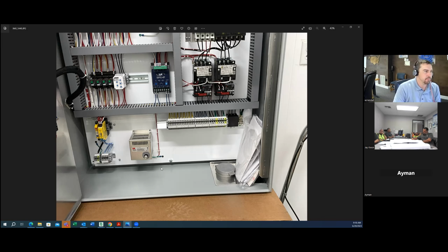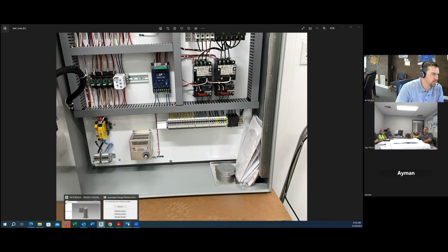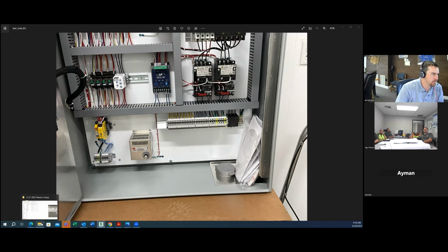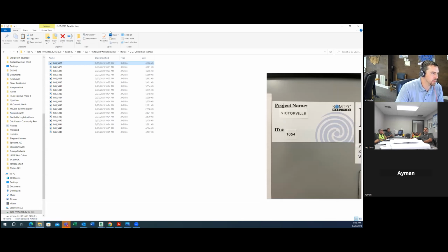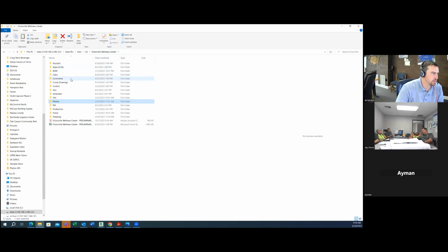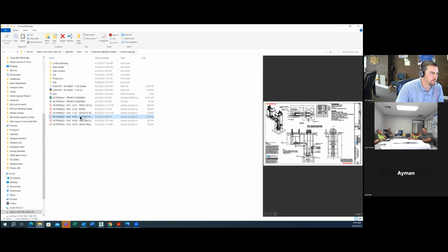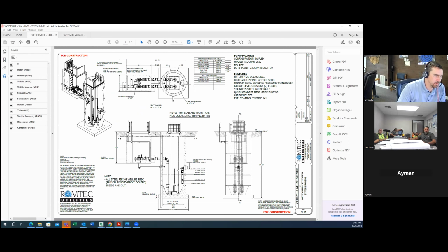Yep, you got 2 sensors, high, low? Yeah, and that's all in one package going down in the wet well, correct? It'll be one 1-inch conduit going to the wet well for the high-low sensor, right? Yeah, the level sensing will all come into one conduit. We have a pressure transducer as the primary level sensing, and then 2 floats for backup level sensing. They can all share that 1-inch conduit.